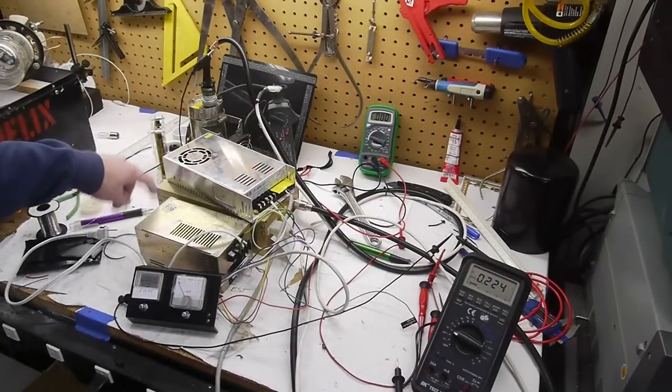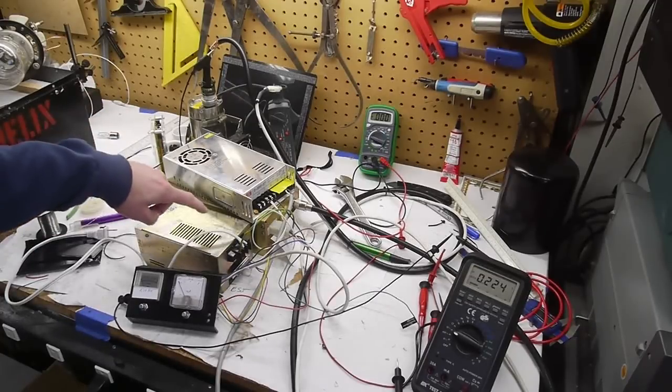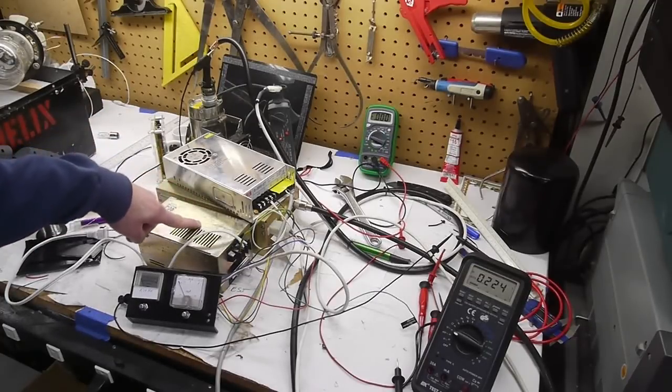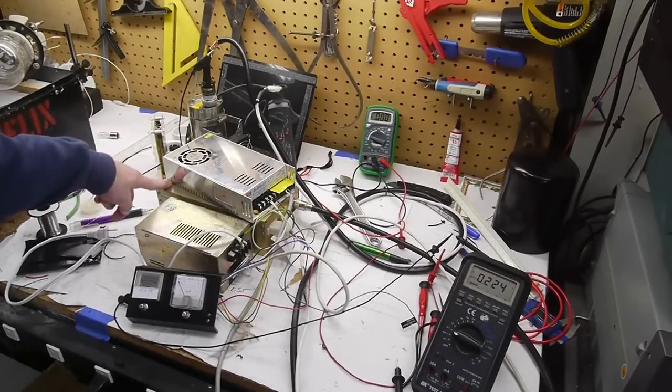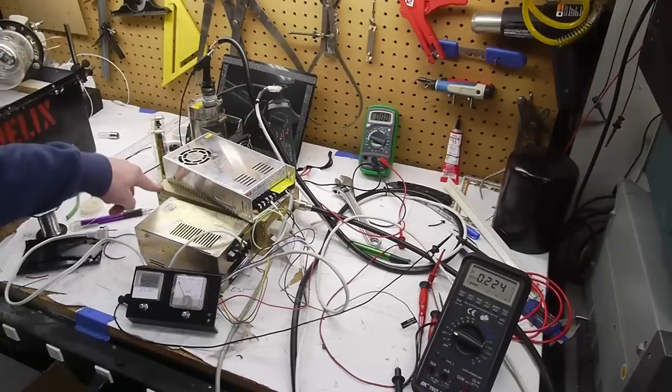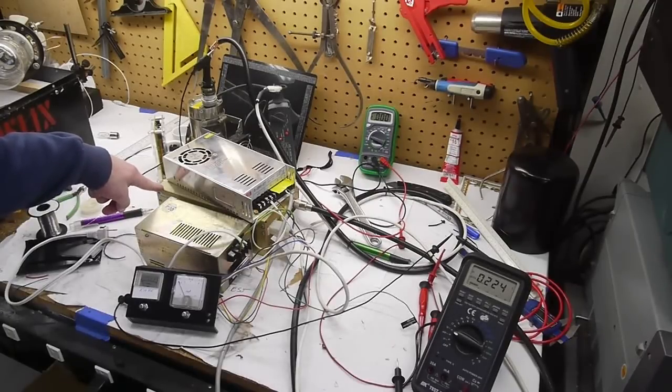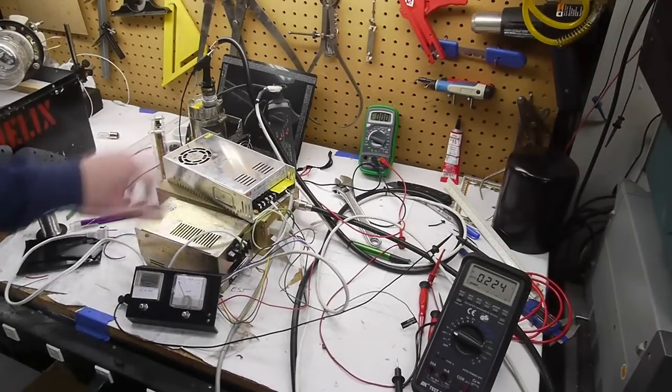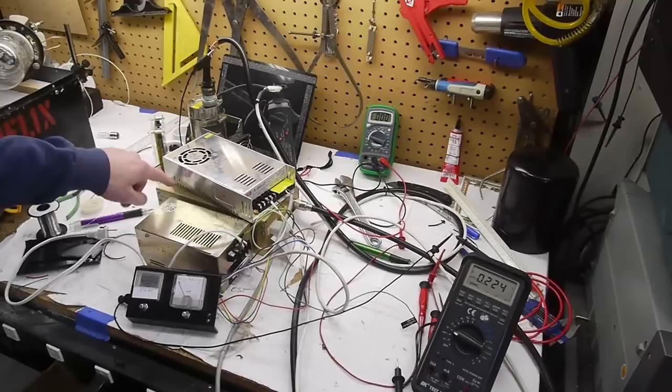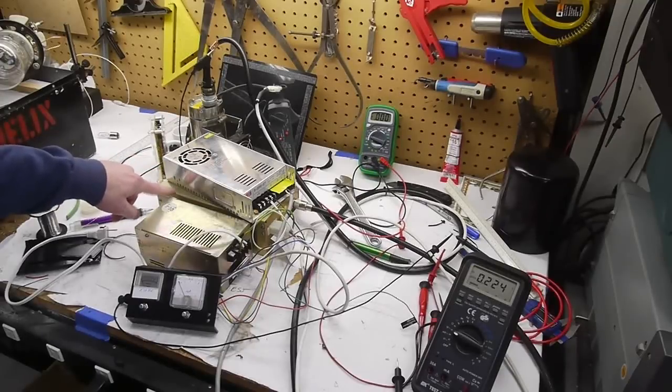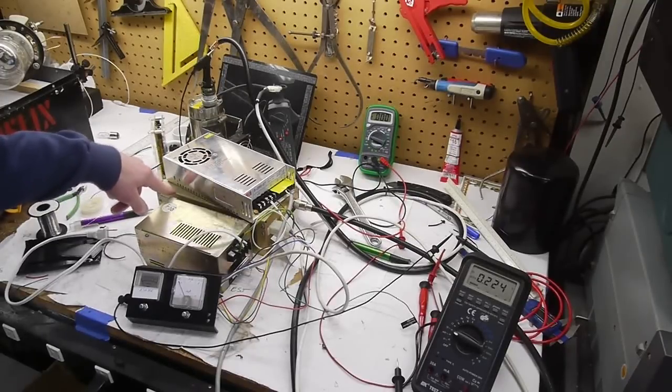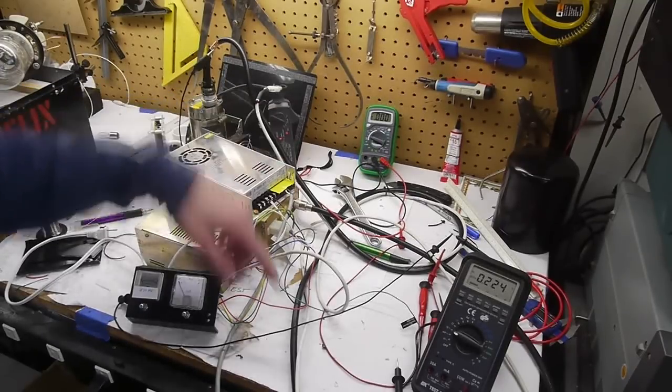I've got this meter set up just to measure voltage coming out of the current sense coming out of the voltage supply. So we actually have two current senses here. One of them is in the filament supply and one of them is from the voltage supply. Since the voltage supply knows how much current it's producing at 50 kV, they should be in agreement. In the original circuit they didn't use the current sense from the high voltage supply, but I soldered a wire on. We'll just check it to make sure.